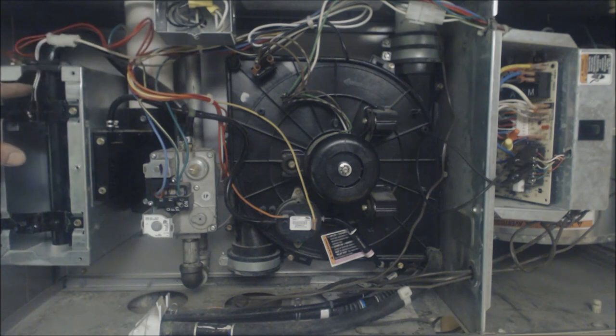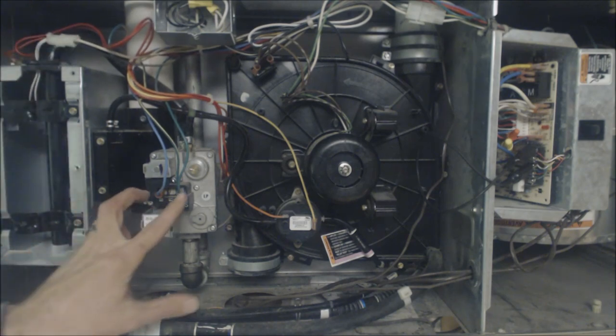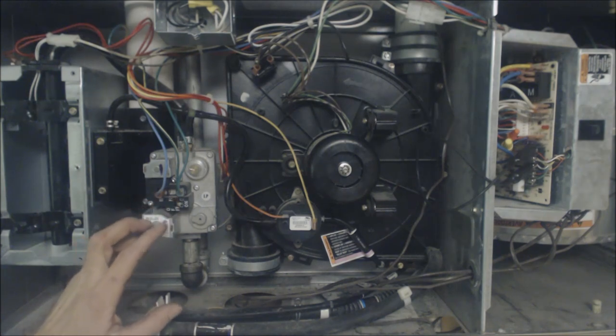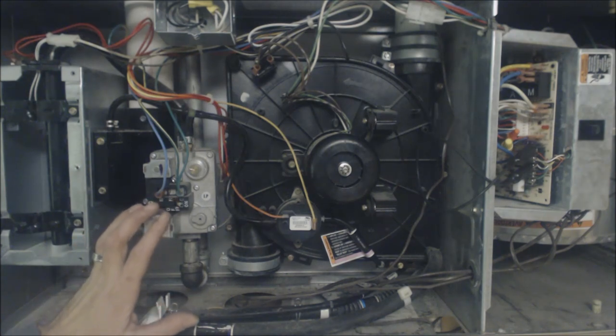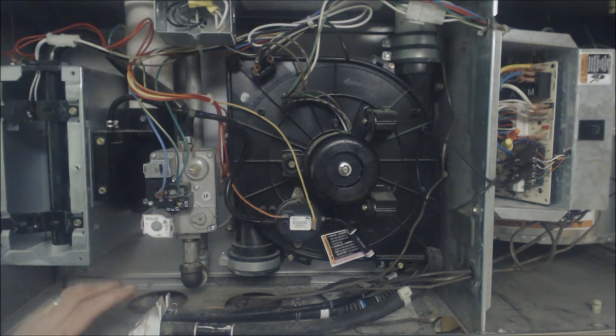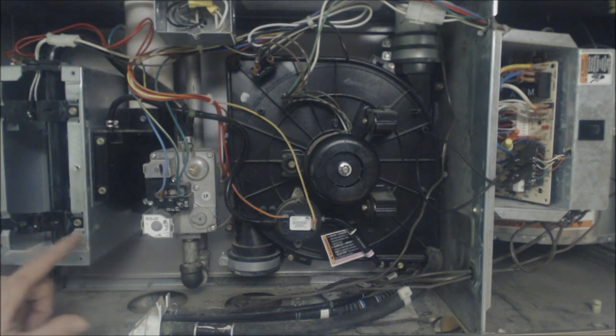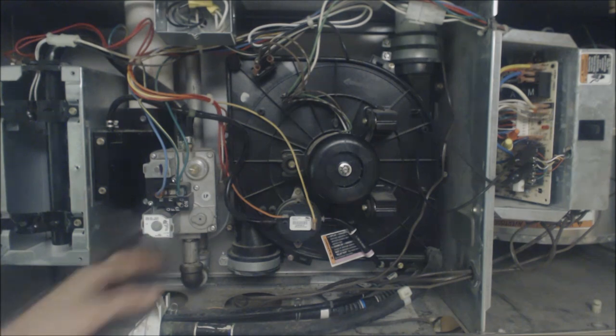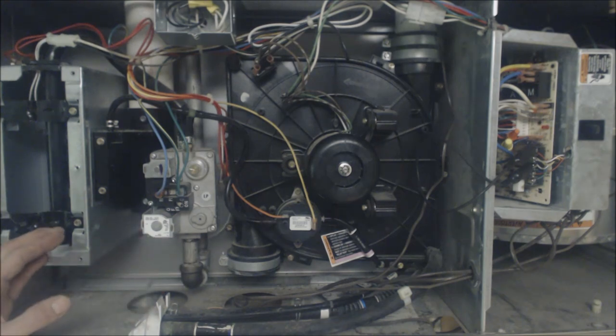Then after that the gas valve gets a 24 volt signal for three seconds and the flame rod has 90 to 110 volts going to the flame rod in here.